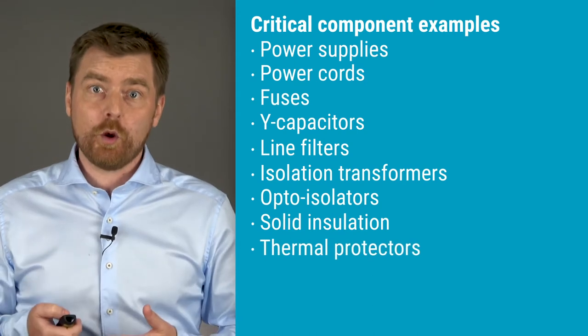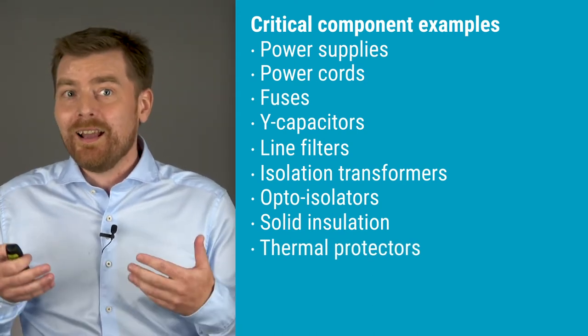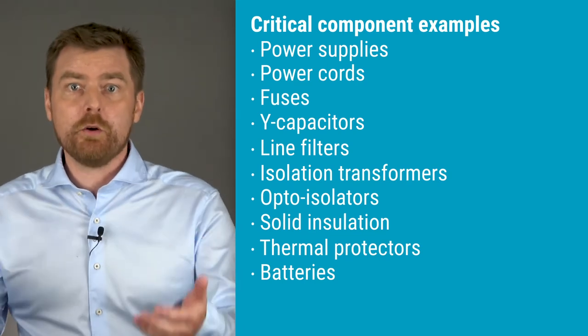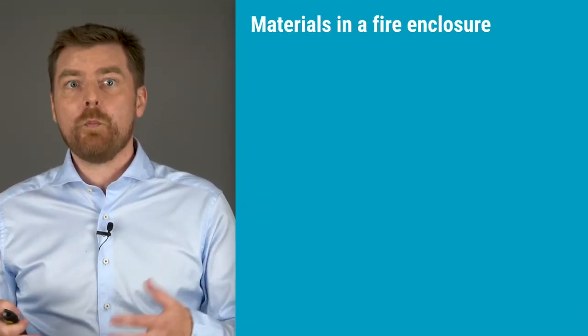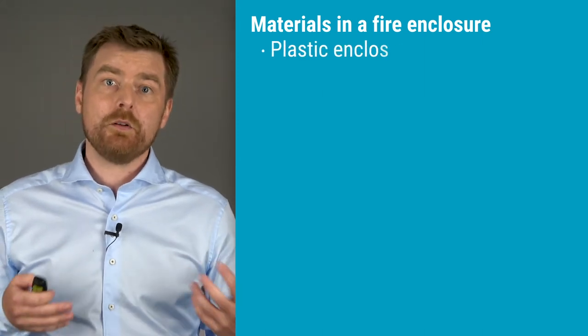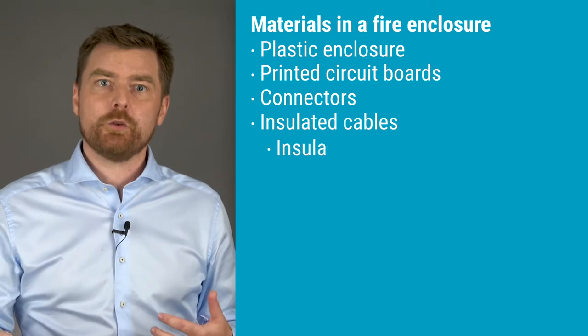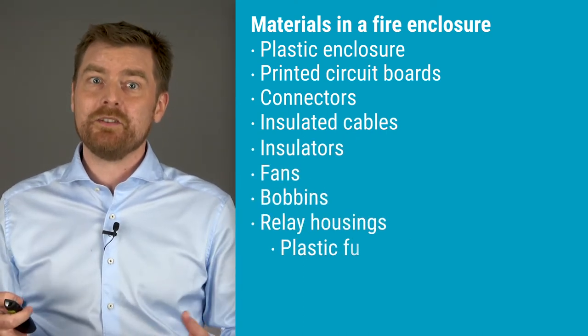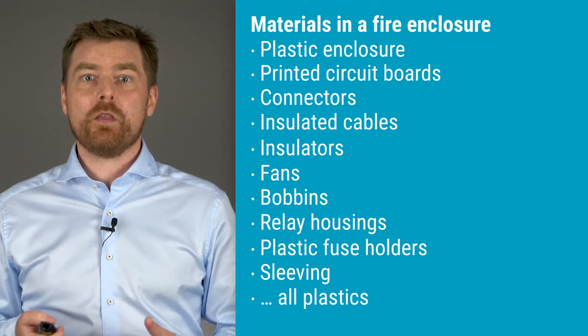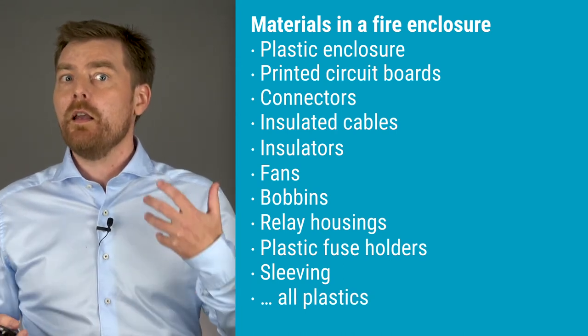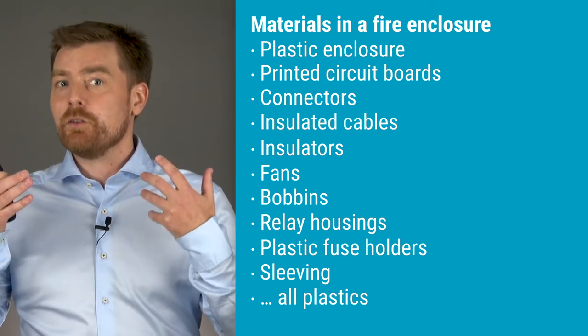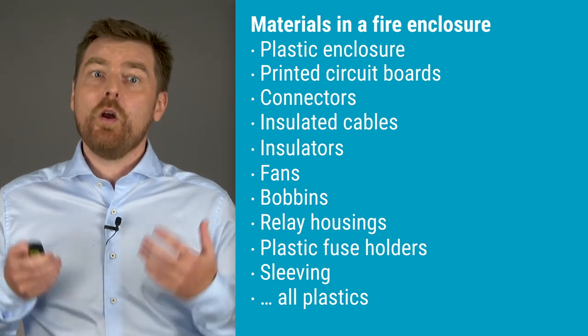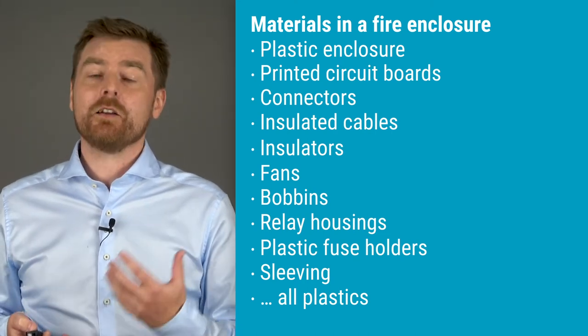A fault in thermal protectors can expose the user to heat. A battery can cause fire or even explode. And connectors can fail to provide insulation. Also, identify materials that are inside or part of a fire enclosure. Examples include the plastic enclosure, printed circuit boards, connectors, insulated cables, and components with plastic parts such as insulators, fans, bobbins, relay housings, fuse holders, sleeving, and so on. In short, all plastics should be identified as critical components.